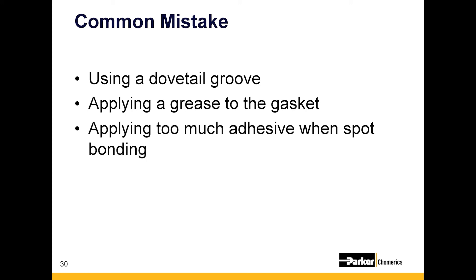Another common mistake is applying grease to the gasket. Grease is meant to reduce friction, and you're not using friction here. More importantly, if you apply too much grease, it can create a dielectric barrier between your housing and gasket. Conductive grease is also becoming less common in applications — it typically isn't needed and can create a galvanic mismatch between the substrate, the gasket, and the grease itself.